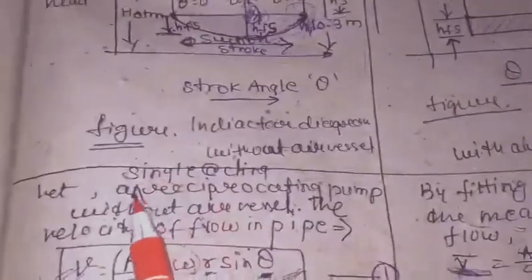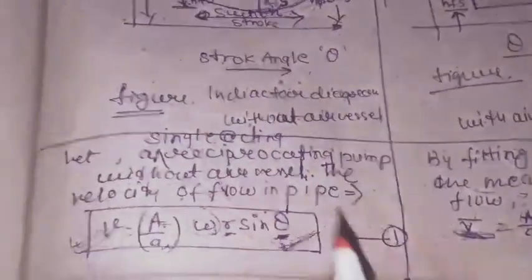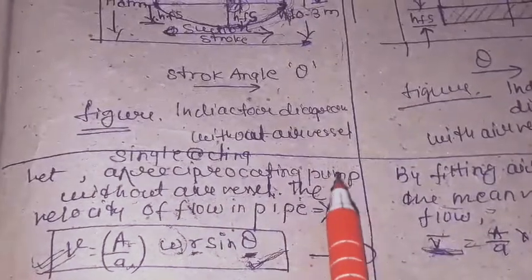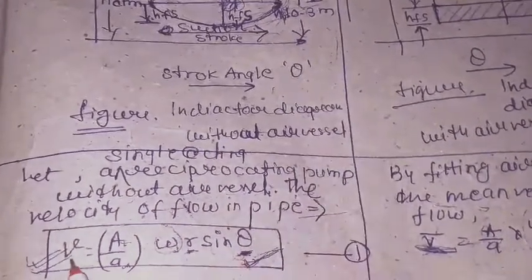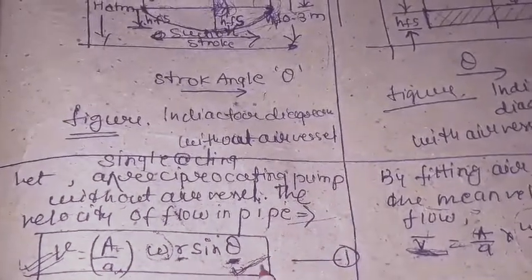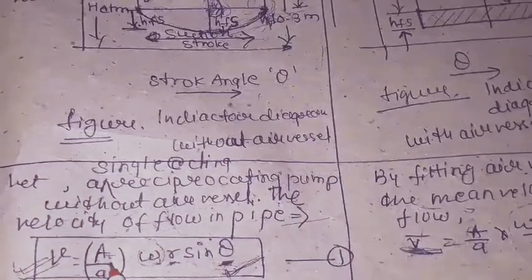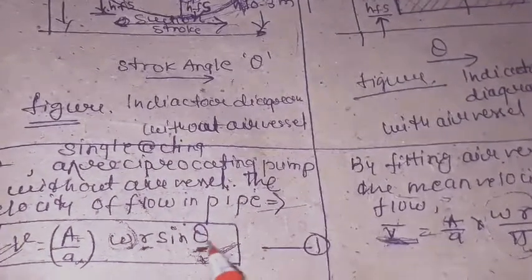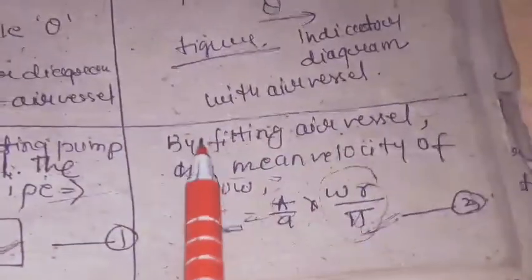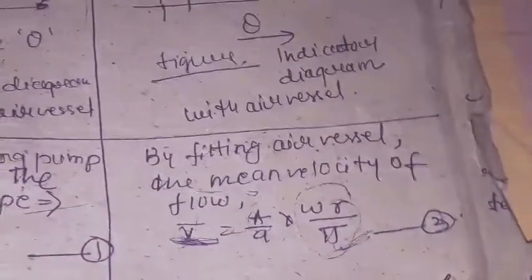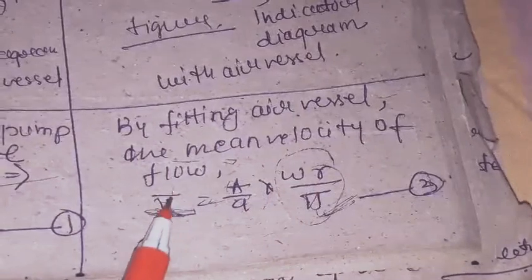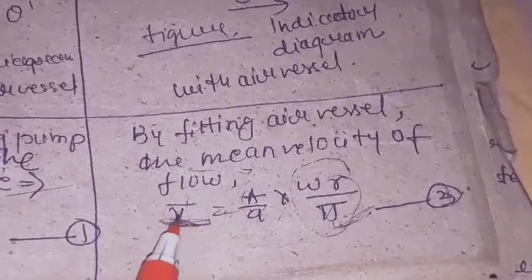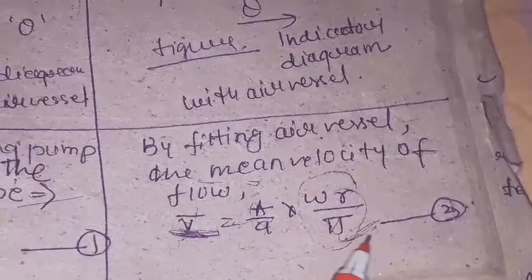For a single acting reciprocating pump when the air vessel is not used, the velocity of fluid inside the pipe is given by: v = (A/a) × ω × r × sin θ, where A is the cylinder area, a is the pipe area, ω is the speed of the pump, r is the crank radius, and θ is the stroke angle. When the air vessel is used, a uniform mean velocity takes place, given by: v̄ = (A/a) × ω × r / π.